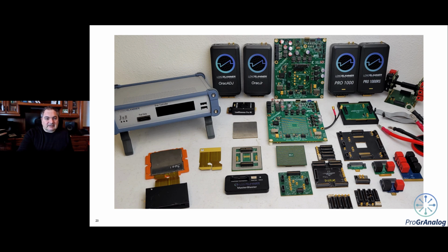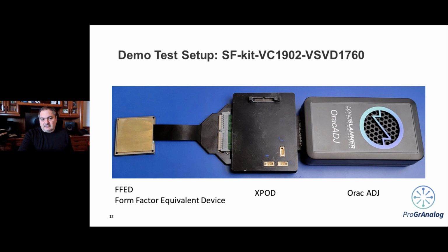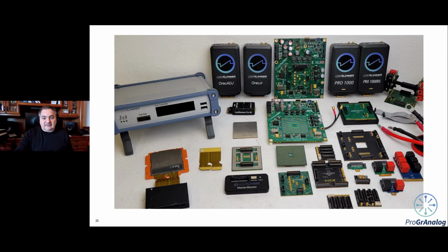So in this example here, the power comes out of the lid of the FFED in the form of heat, right? So you want more DC, it dissipates more heat. So you just need a better cooling solution. If you want to do more DC, but you don't have a down solution like the FFED, you can put down a passive solution, and you can see like in the middle, there's these large, you can't see my cursor, can you?